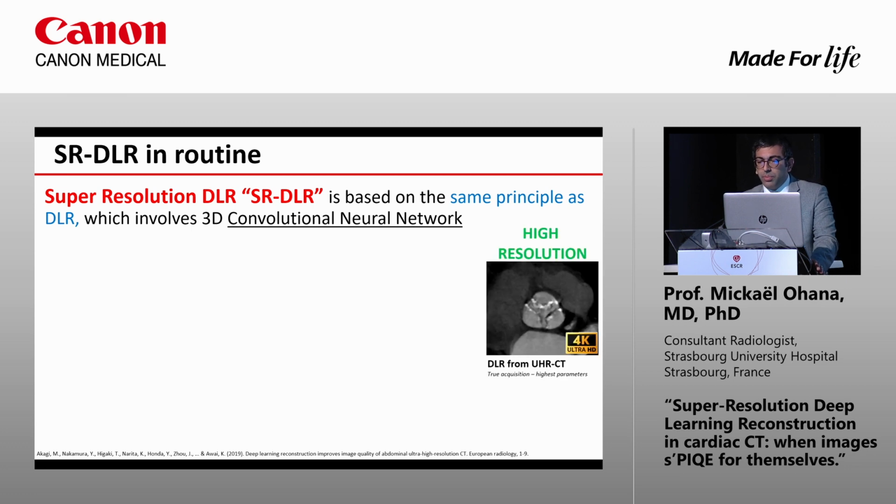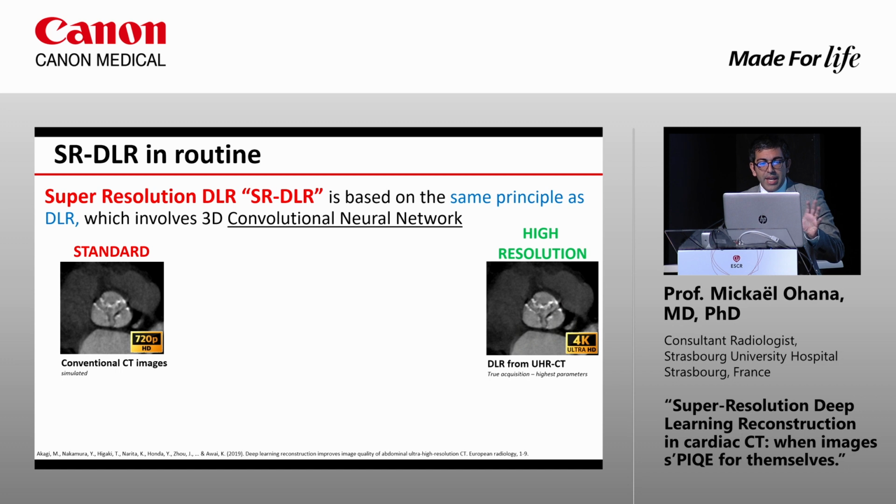SR-DLR is based on the exact same principle as DLR. It's based on convolutional neural networks, and very briefly, the target images for the training are high resolution acquisitions from UHR-CT. The base images for the input are simulated conventional CT images.